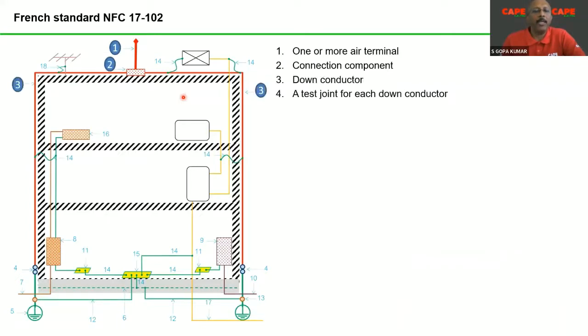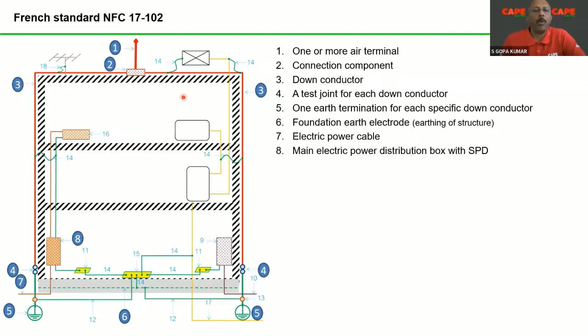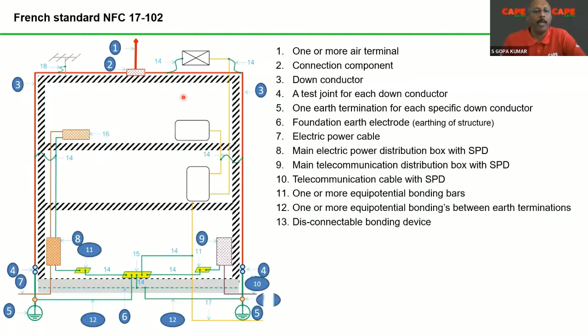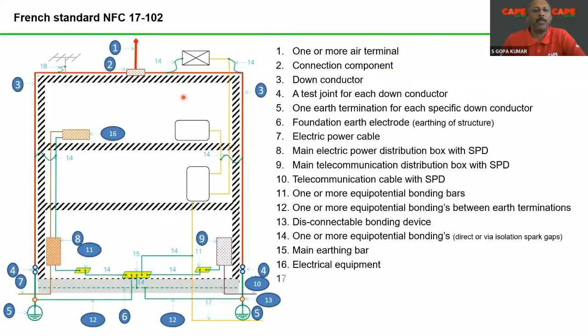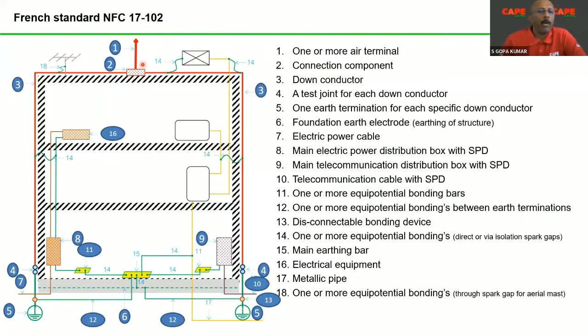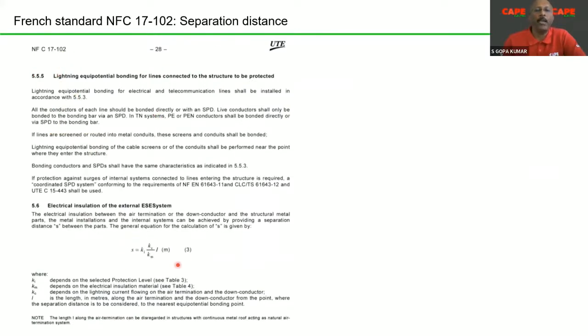If we look at the French standard, it does not explain ESE as one rod, one down conductor and one earthing. It explains a proper equipotentially bonded, proper lightning protection system consisting of several components. So basically, the French standard is similar, I would say, over and above IEC 62305, with some more arrangement. If you read the NFC standard, it explains that you make a Pakka lightning protection system as per 62305, and over and above, you make some additional arrangement like an ESE air terminal. That means the story which is the propaganda made in India, one rod, one down conductor, one earth electrode, is absolutely wrong. This is never written in the National French Code. Now, anyway, our subject is not only that. Our subject is separation distance. In the same French Code, you can find the separation distance calculation.